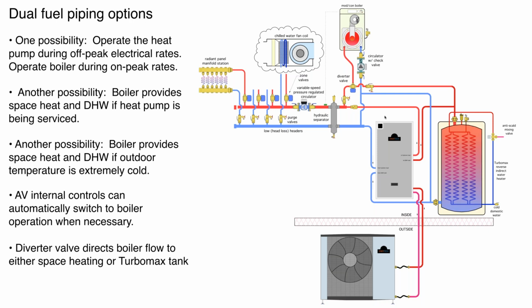Okay. The AV unit, the Enertech heat pump, does have the logic to know when that auxiliary boiler is connected, and it can operate that boiler when necessary. Okay. So this shows a diverter valve. The output that is coming basically from the heat pump right here, this would be the space heating heat output. The diverter valve is for the auxiliary boiler. That determines whether the output from the auxiliary boiler goes to the space heating system or over here, into that TurboMax indirect water heater. So this is providing a backup both to space heating and also to domestic hot water.